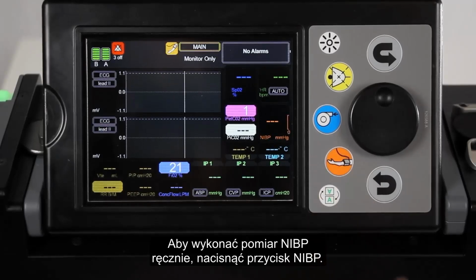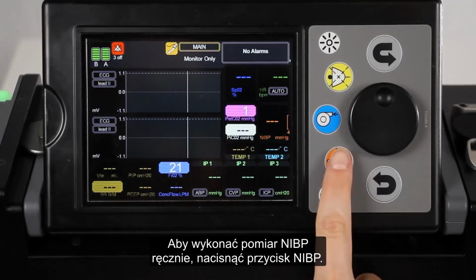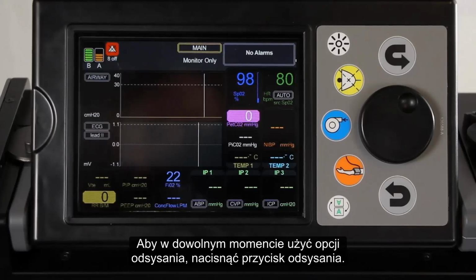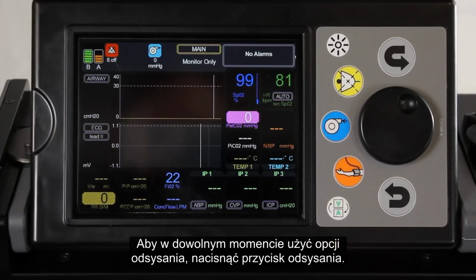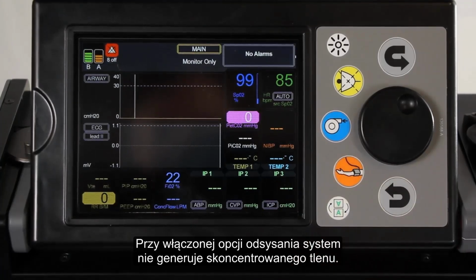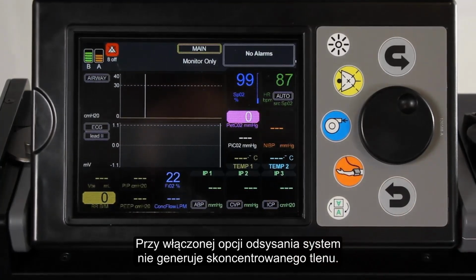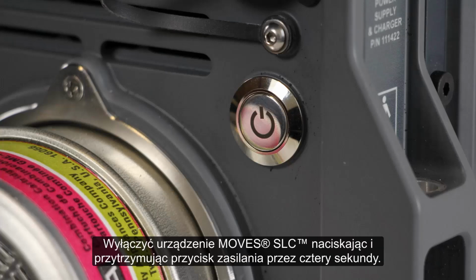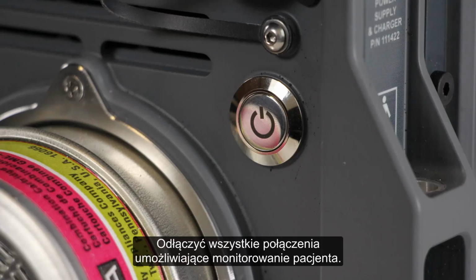To take NIBP manually, press the NIBP button. To use suction at any time, press the suction control button. When using suction, the system will not generate concentrated oxygen. Shut down Moves SLC by pressing and holding the power control button for 4 seconds. Remove all patient monitoring connections.